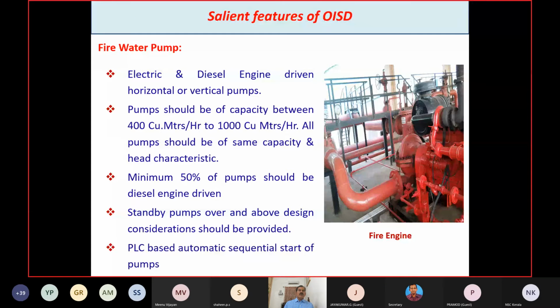So standby pumps over and above the design considerations should be provided, and PLC based automatic sequential startup of pumps should be ensured. So the pump logic should be available.